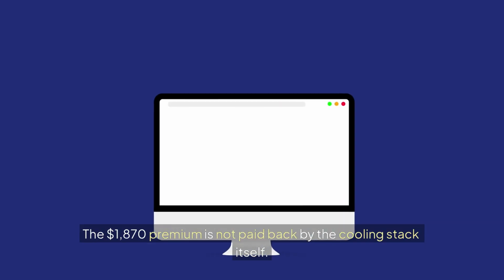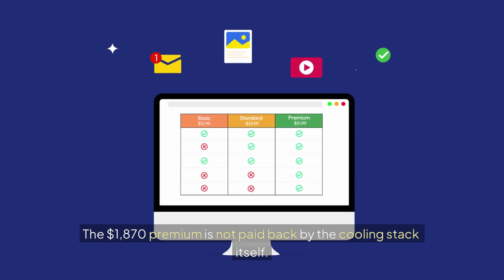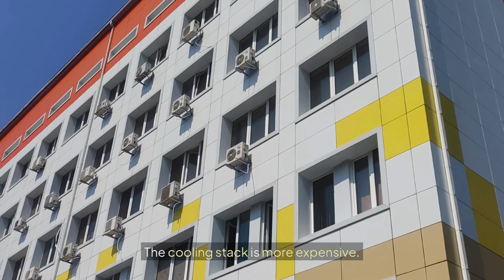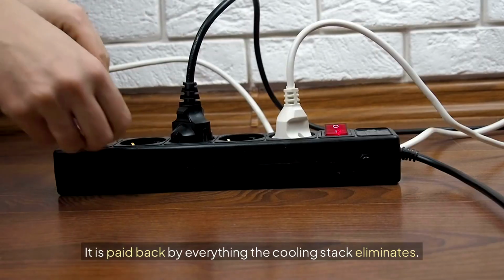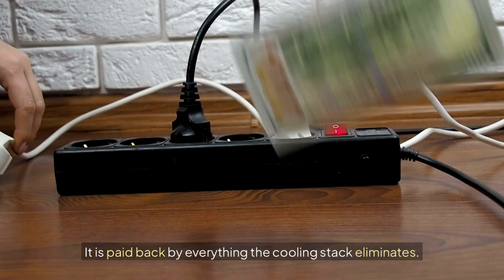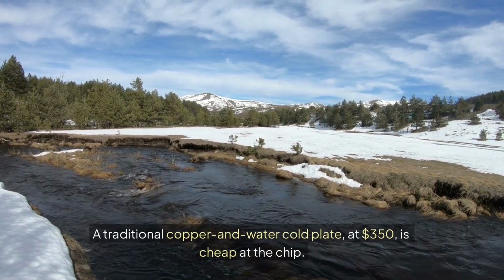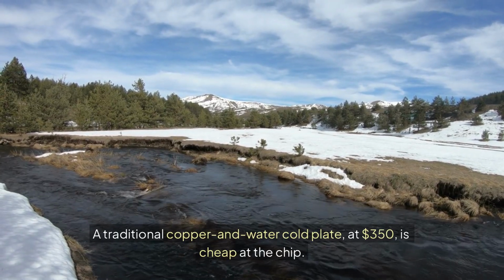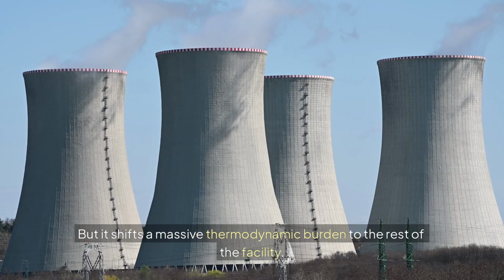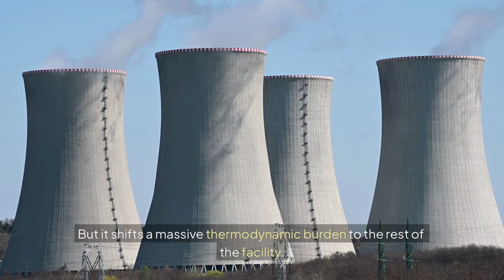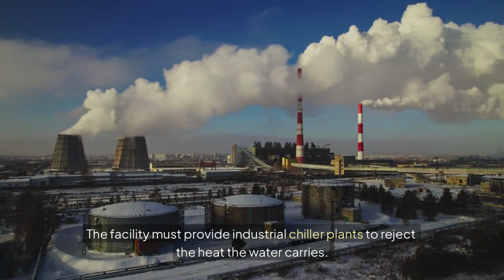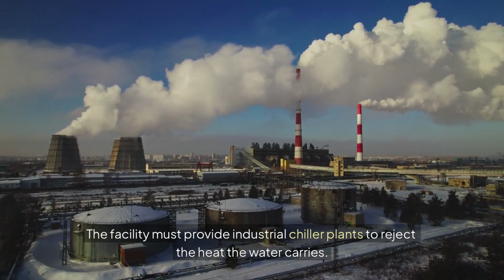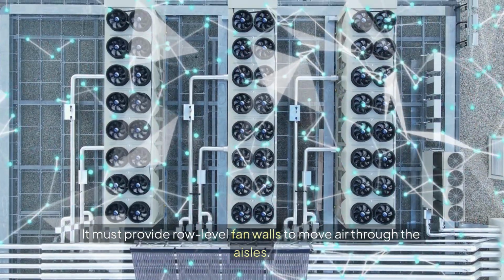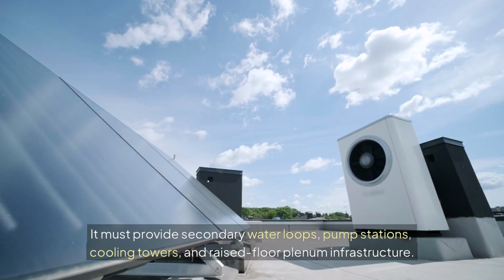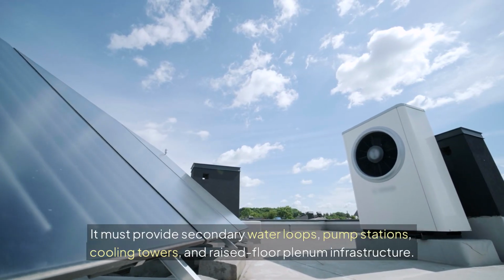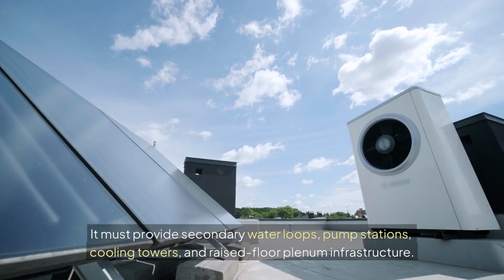The $1,870 premium is not paid back by the cooling stack itself. The cooling stack is more expensive. It is paid back by everything the cooling stack eliminates. A traditional copper and water cold plate, at $350, is cheap at the chip, but it shifts a massive thermodynamic burden to the rest of the facility. The facility must provide industrial chiller plants to reject the heat the water carries. It must provide row-level fan walls to move air through the aisles. It must provide secondary water loops, pump stations, cooling towers, and raised floor plenum infrastructure.